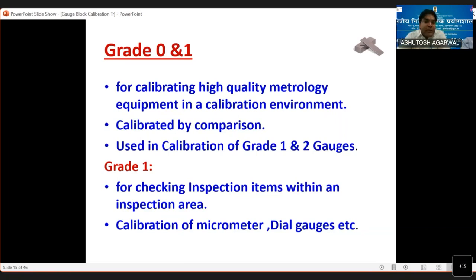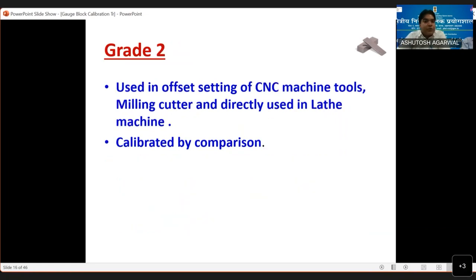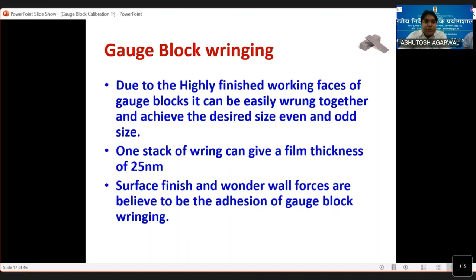Or you can calibrate a micrometer or dial gauge using the first one. Then the second is just used for the offset setting in CNCs, mill, lathe and so on. And it's also calibrated by comparison. So that is the usage, where you have to use which gauge, we should know properly. But to measure, one of the important things is wringing.